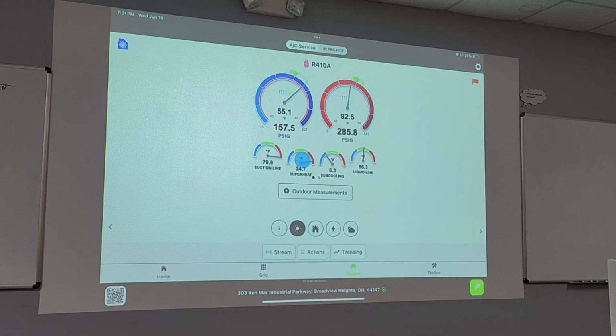And then superheat is low. Now you tell me why, it's a TXV. Why could the superheat be low, or why could the superheat be high on a TXV system? I mean, yeah, it's a little bit low on refrigerant, but you should still have a solid column of liquid hitting that TXV with 6.3 degrees subcooling. So only real reason why the superheat could be high is the TXV's not opening far enough. Well, the suction line probe's not in the right place. Right. Now it's a package unit, so really the suction line probe can't be that far away. If you're on a split system with the line set going 1,000 feet across a hot attic, you would kind of expect the superheat to be a little bit high. But on a package unit, the suction line's not that long.